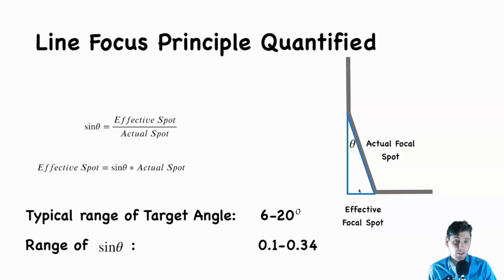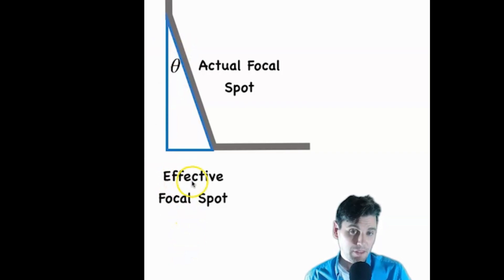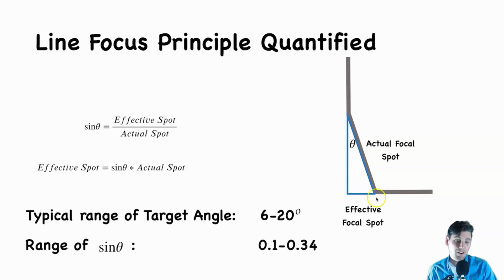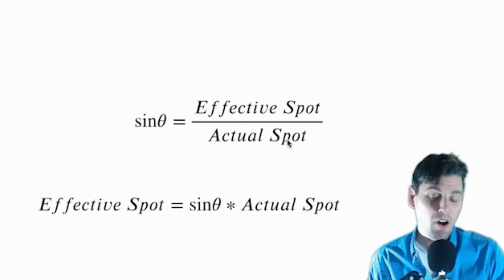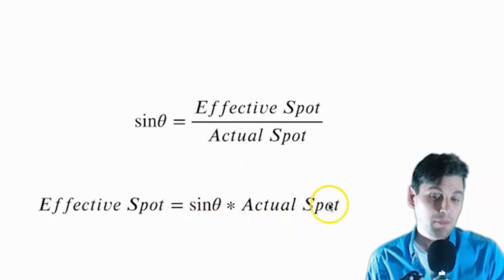If we quantify that, the x-ray tube has a target angle as shown here. Right here is the actual focal spot where the electrons are hitting, and right here is the effective focal spot where the x-rays are coming out. If we remember from high school math, for these right triangles, the definition of the sine at this angle is the opposite over the hypotenuse. So the sine of this angle is the effective focal spot divided by the actual focal spot. Solving for the effective focal spot, we get: effective focal spot equals sine of theta times the actual focal spot.